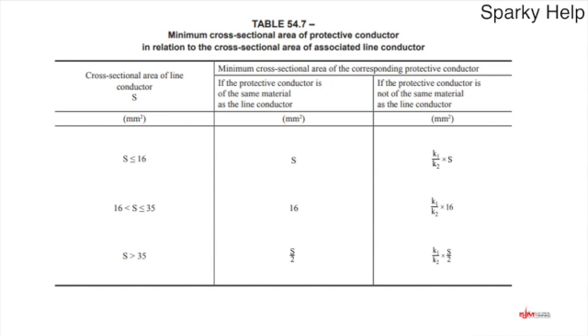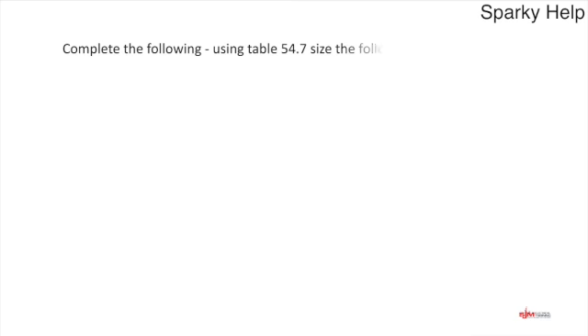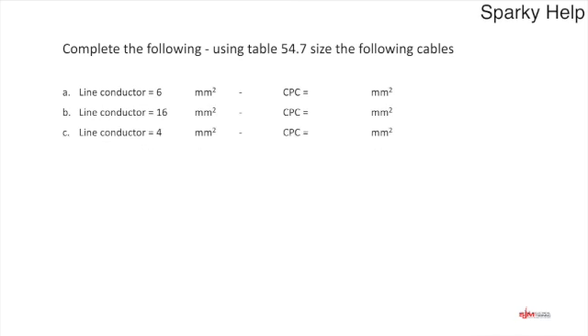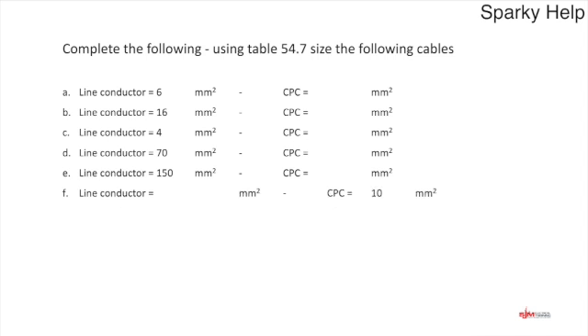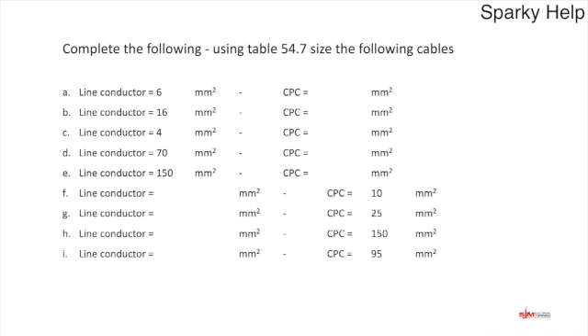However, if you were to put a 95 mil cable in, half of 95 is not a round number, so you don't use a half size of 95, but the next size up would be a 50. So a 50 mil is what would go in. The best way to look at this is to have a look at some questions that I've put together. We've got line conductors in different sizes, but then I swap it around a bit. For F, I've said okay, this was your CPC, so what size line would you get for each of these?